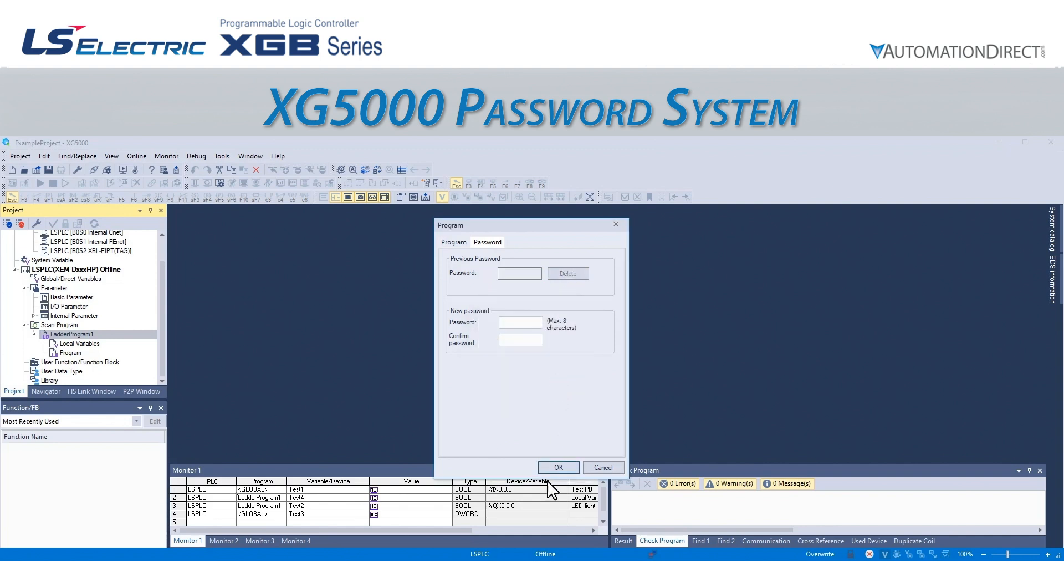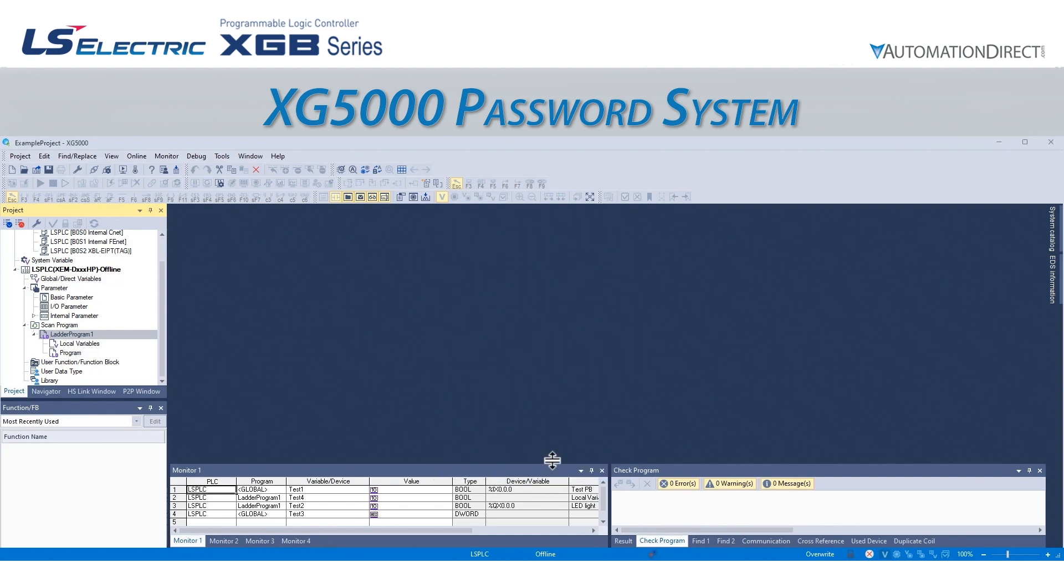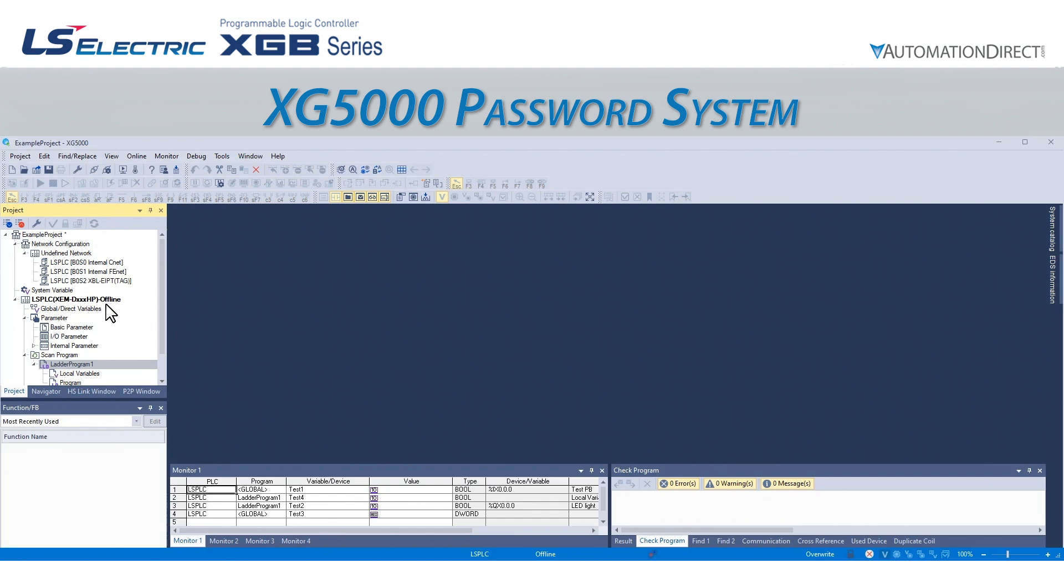It is important to note that these steps will password protect a program that has been written to a PLC, even if someone reads it back from the PLC. Setting the Project password, however, only protects the offline project. The project written to the PLC will still be able to be read back by someone else without a password. To protect the PLC itself, it is necessary to add a PLC password.